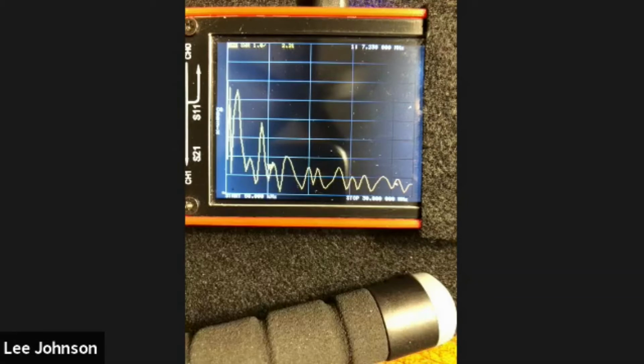Okay. Then you do the calibration. Once you've got that in your head, then you do the calibration, because you know what frequency span you're going to operate on, what you're looking for, and what scales of division you want on SWR or some other chart. If you want to scale the Smith chart to 75 ohms instead of 50 ohms, you can do that as well. So once you get that done, then you do the calibration.